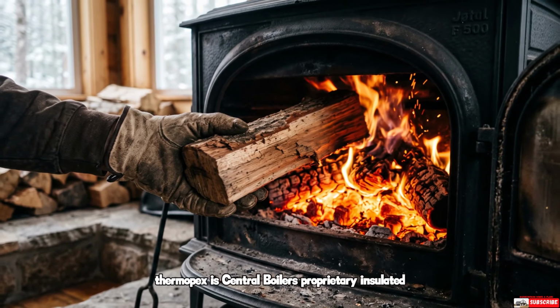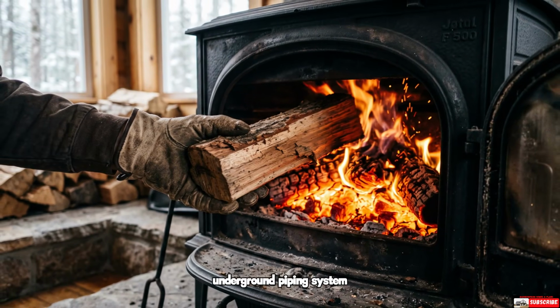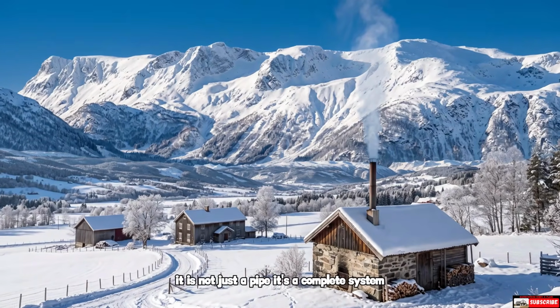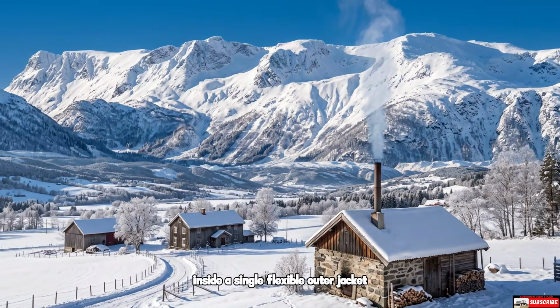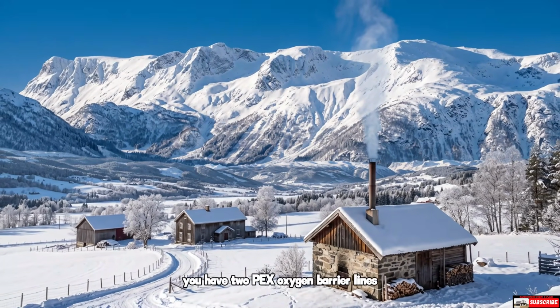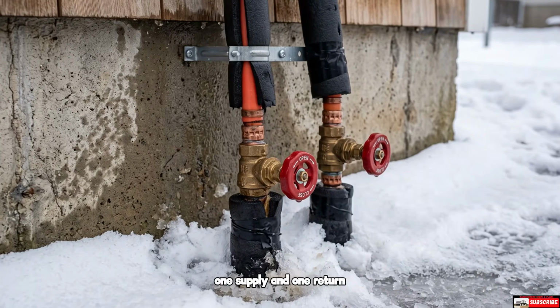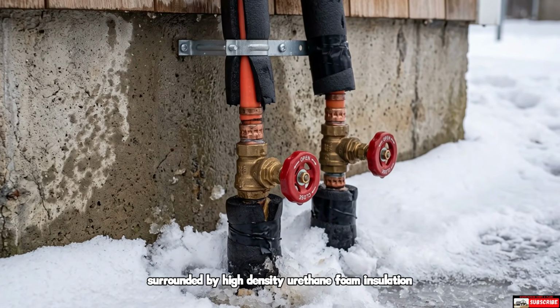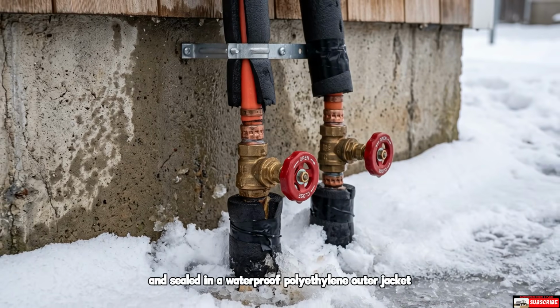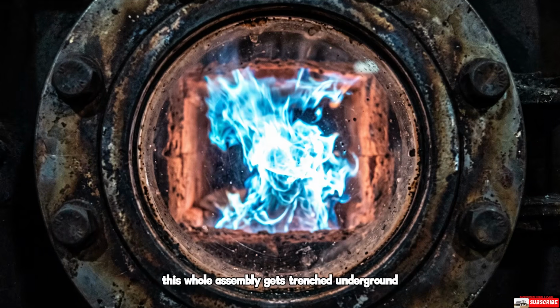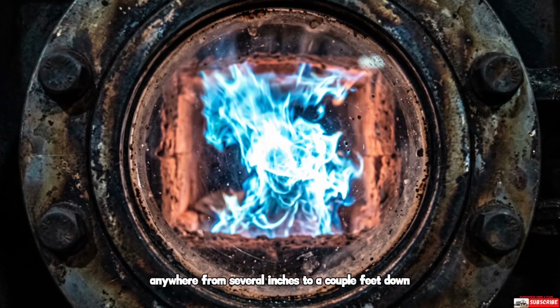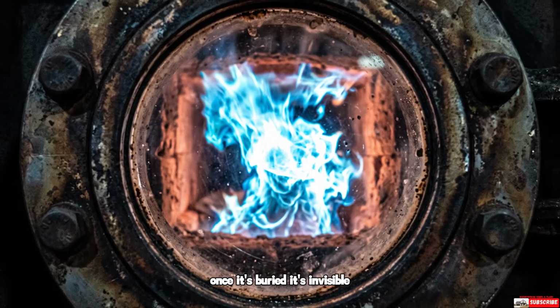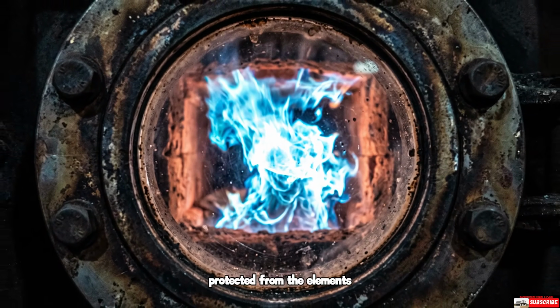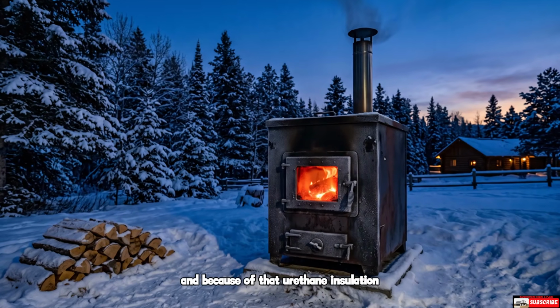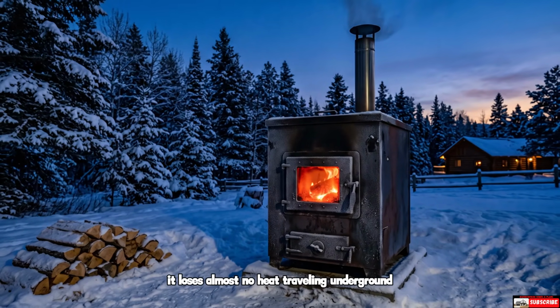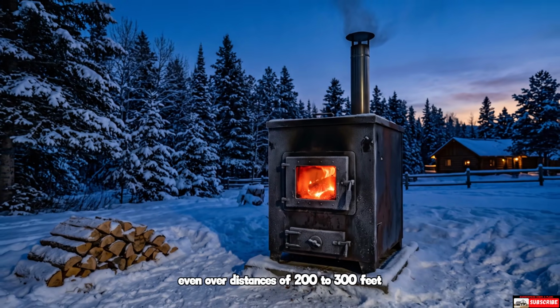ThermoPEX is Central Boiler's proprietary insulated underground piping system. It is not just a pipe, it's a complete system. Inside a single flexible outer jacket, you have two PEX oxygen barrier lines, one supply and one return, surrounded by high-density urethane foam insulation, and sealed in a waterproof polyethylene outer jacket. This whole assembly gets trenched underground anywhere from several inches to a couple feet down. Once it's buried, it's invisible, protected from the elements, and because of that urethane insulation, it loses almost no heat traveling underground even over distances of 200 to 300 feet.